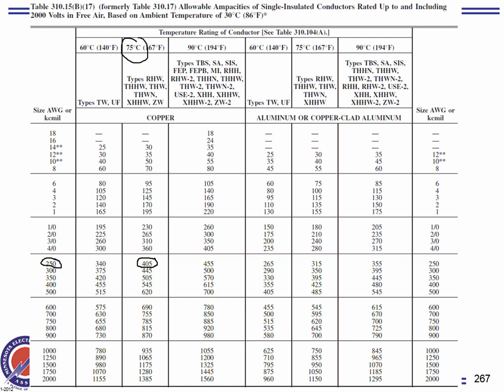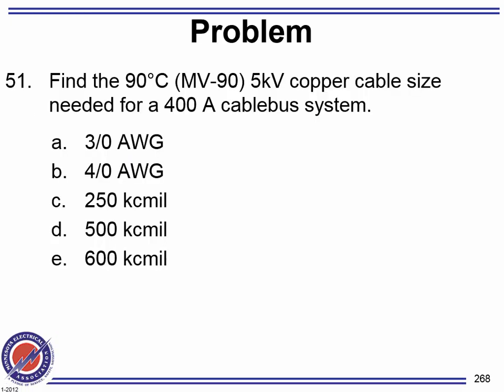Look how much 500. Look at this. If you have a 500 kcmil conductor, look how much current that dude can carry. Anybody remember how much a 500 kcmil conductor can carry in a conduit? I can tell you, it can carry 380 amps because we use it all the time. So we went from 380 to 620, almost doubled the amps, if you put that cable up in the air, or in this case, a cable busway system, a manufactured enclosure, spaced appropriately, where heat can dissipate. The reason we derate is that they allow the conductors to carry fewer amps because you're trapping heat inside the conduit. There's no space. It's not like air, where heat can escape.